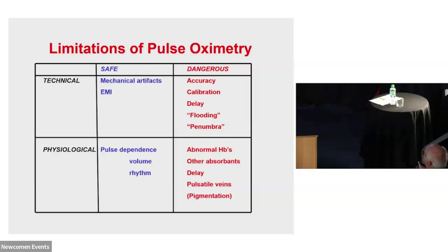Some of them have a delay. The delay is when it might be reading a good value, and yet suddenly that value sticks until the pulse oximeter picks it up again. And it might not pick it up because the patient has died or got very low blood pressure. But instead of showing that it's not working, it just delays and holds on to the main signal that was there in the first place.